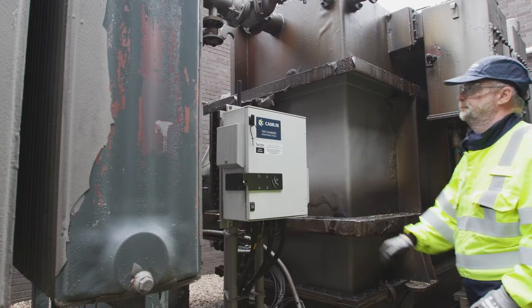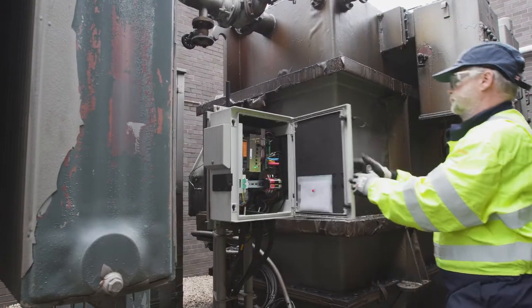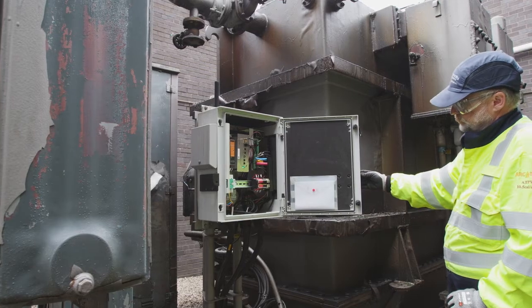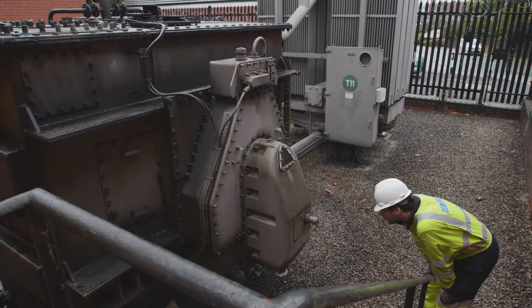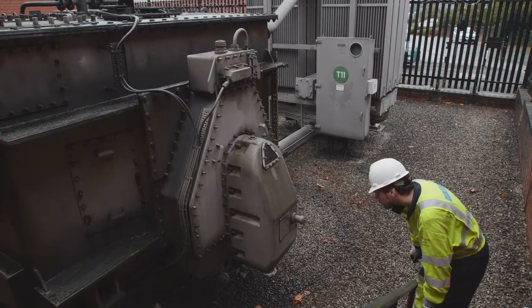So generally that's maintained on a time-based period. What we're trying to do by using the tap changer monitoring equipment is by affixing acoustic sensors to various locations around that part of the transformer, and by monitoring the sounds generated during each operation and feeding that through an algorithm which can detect changes in those noises, is to pick up potential sources of failure before they develop into a problem. So traditionally, if a tap changer degenerated to the point where it failed, the first we'd know about it, if it wasn't picked up on a time-based maintenance, would be when you had alarms due to control.